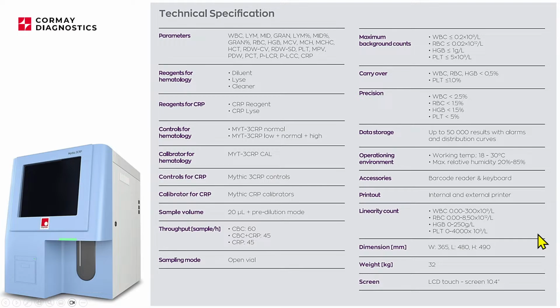In terms of linearity, we have the range between 0 and 300,000 for WBC. RBC is from 0 to 8.5 millions per microliter. It really depends what units you are using. Here we have from 0 to 300,000 per microliter, and here we have millions per microliter. For the hemoglobin it is from 0 to 25 grams per deciliter.